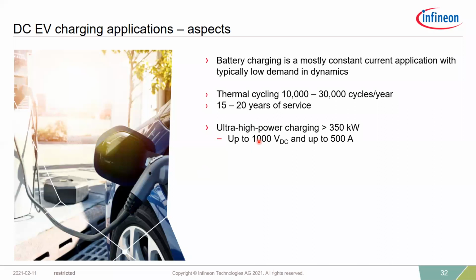That's the reason with the existing voltage level, for example 600 volts, the current would be way too high. That's why you have to go for a higher voltage category, like 1000 volts DC - then only higher charging is possible. You also need liquid cooling for the cable, otherwise you cannot make it thinner.